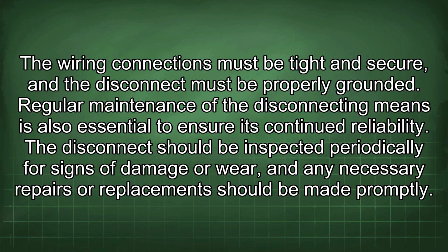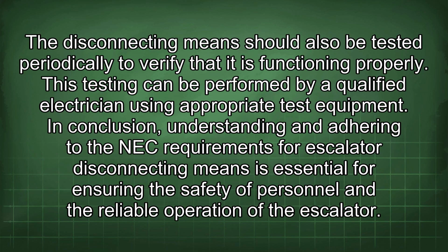Regular maintenance of the disconnecting means is also essential to ensure its continued reliability. The disconnect should be inspected periodically for signs of damage or wear, and any necessary repairs or replacement should be made promptly. The disconnecting means should also be tested periodically to verify that it is functioning properly. This testing can be performed by a qualified electrician using appropriate test equipment.